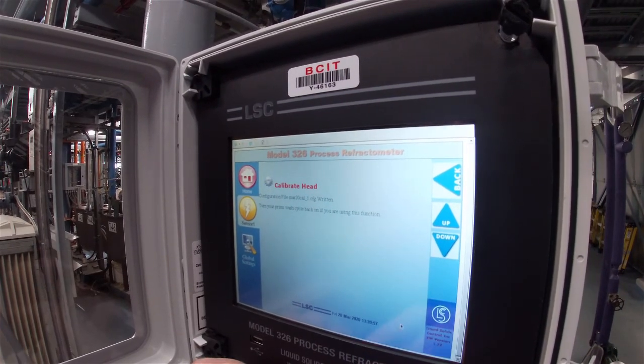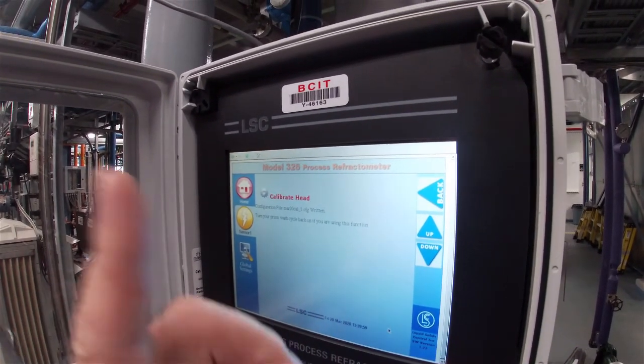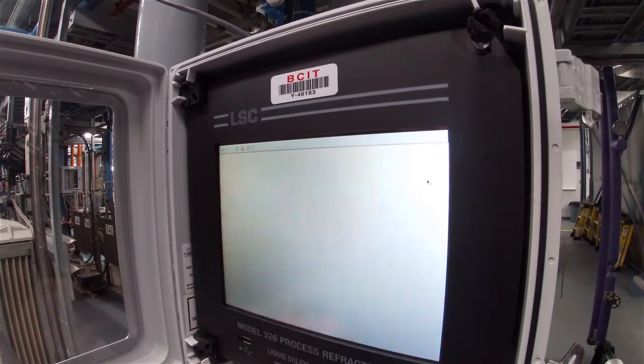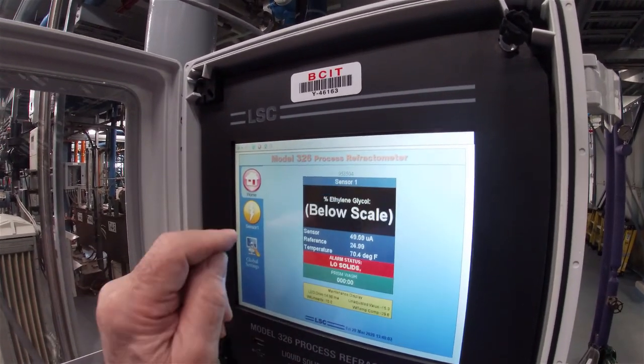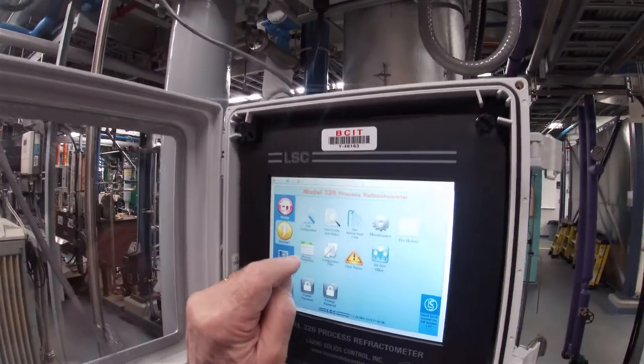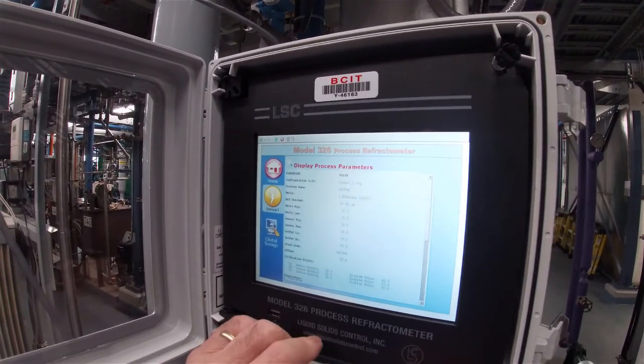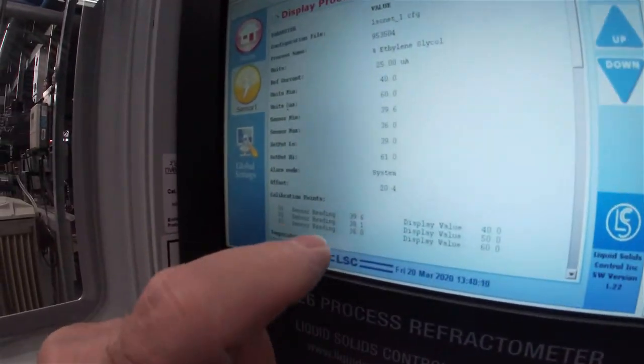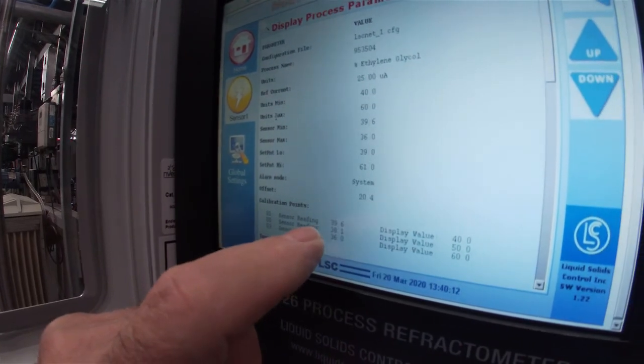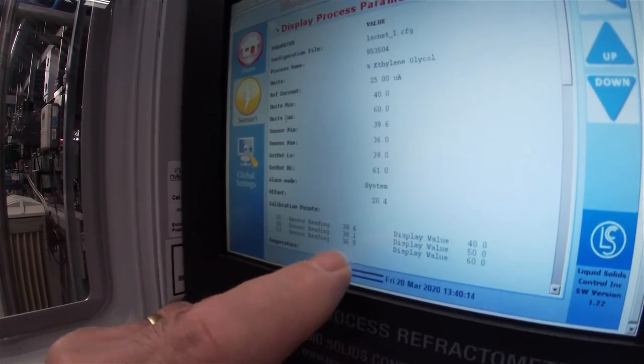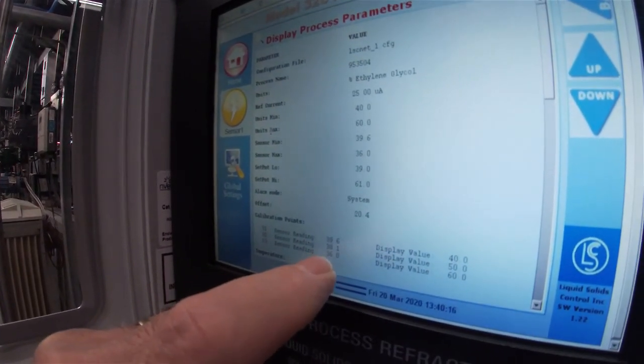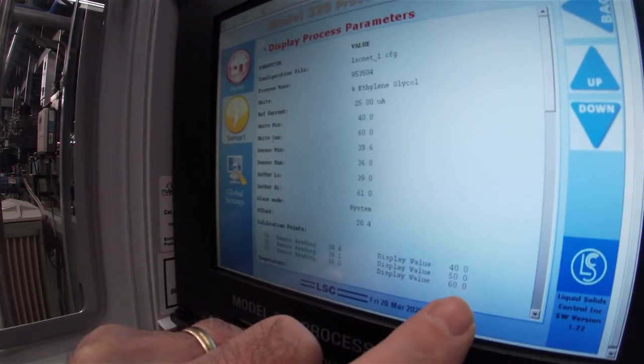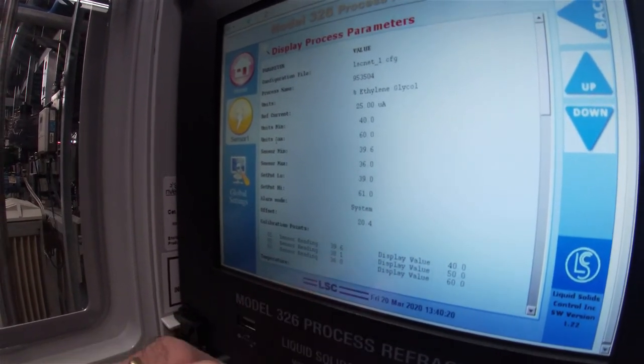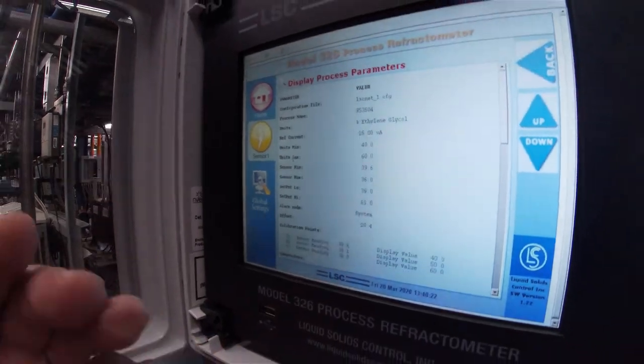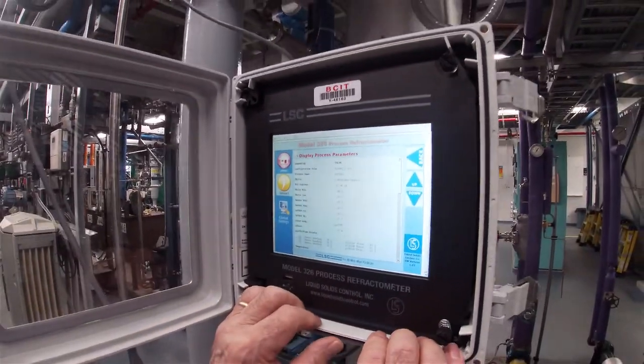Okay, so now it's telling us basically to put it back. So before we do that, let's go back and take a look at the process parameters. And in process parameters, we can see now that our 40% ethylene glycol was 39.6 microamps, our 50% ethylene glycol was 38.1 microamps, and our 60% ethylene glycol was 36 microamps, which is the way we expect the numbers to be running.